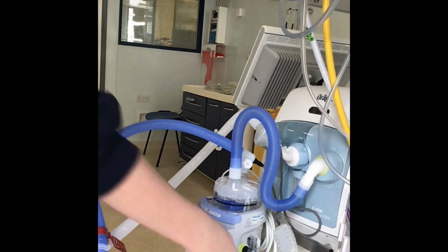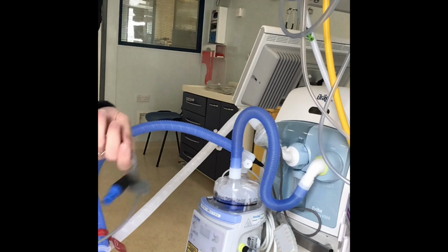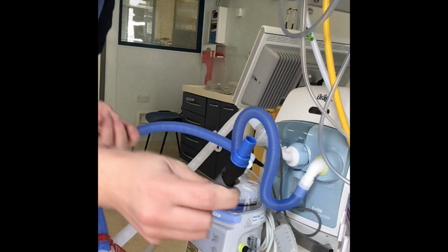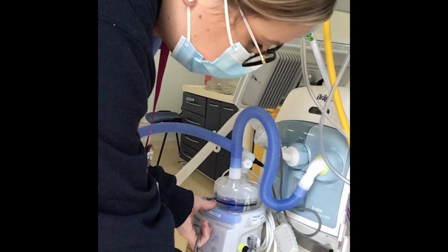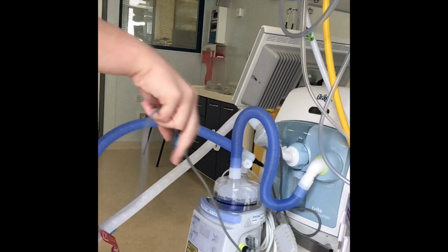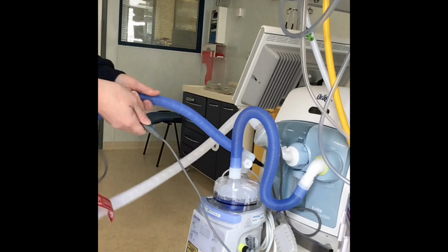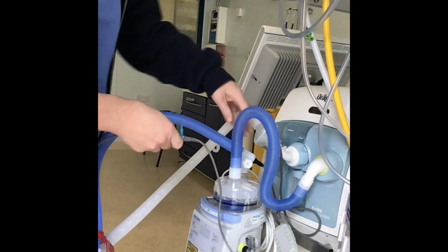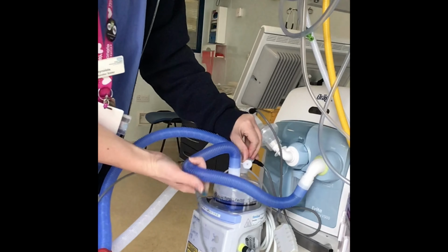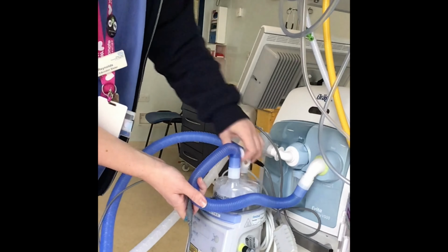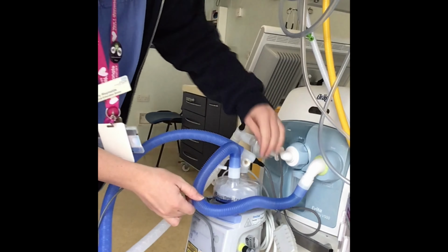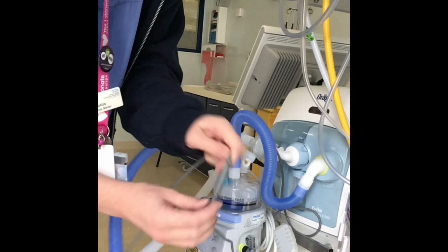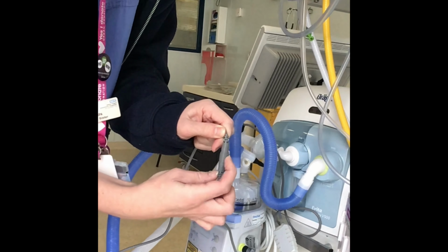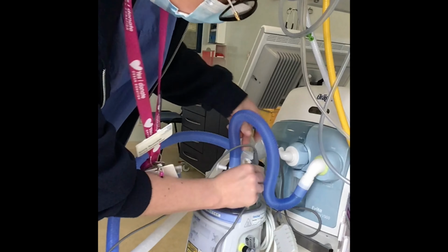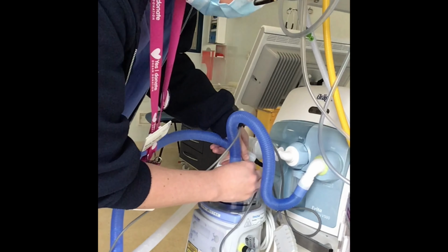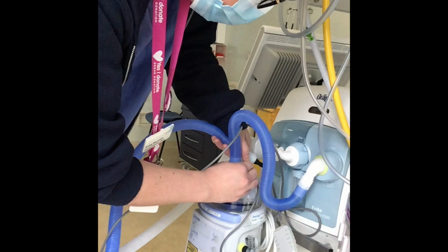Second cable, so starting at the actual humidifier again, you've got a blue hub and a blue connector. So again, match those up. These blue connectors connect onto this long blue part of the tubing. You've got a connection here. This plastic bit will just come off, it's like a covering. You've got a catch here, and on part of the wires you've got a little lip, so this will push in and the lip will go underneath the catch. You'll hear a click.